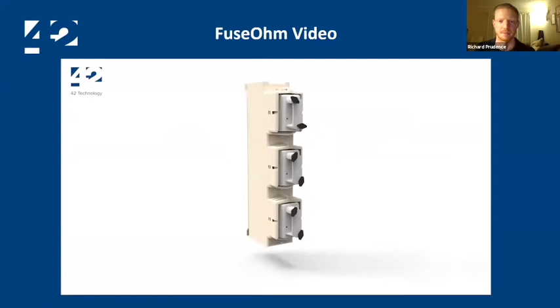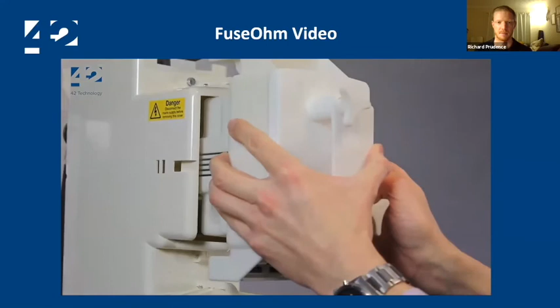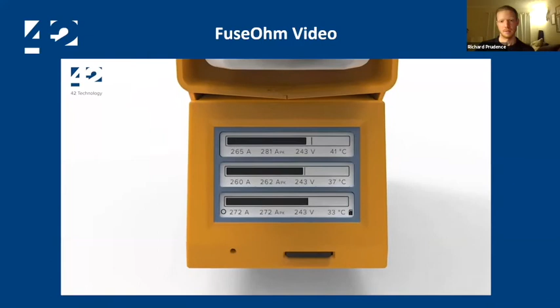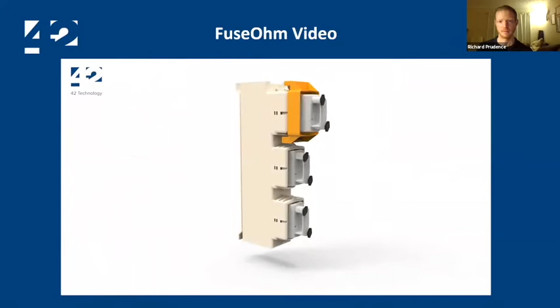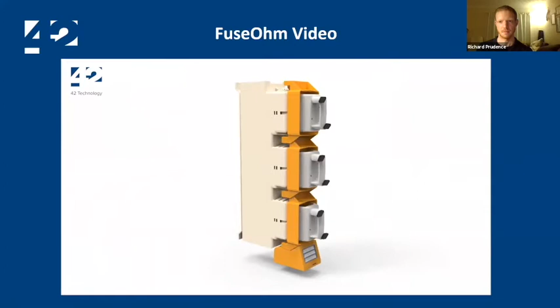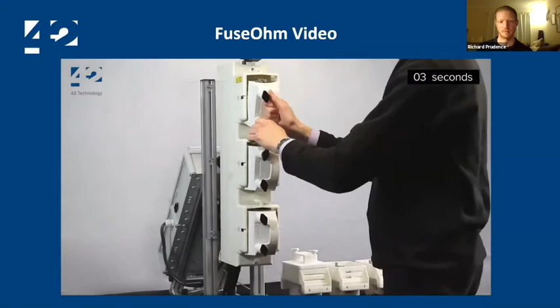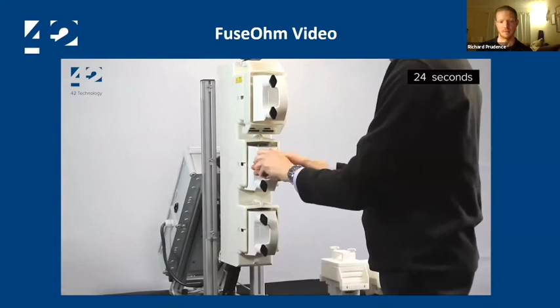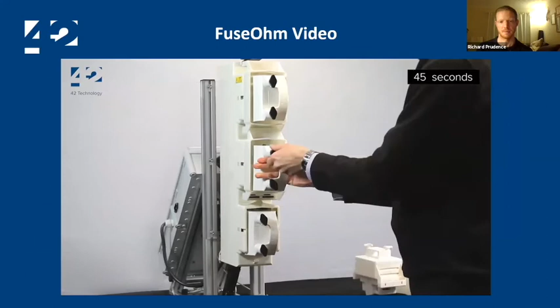Introducing FuseOhm, an innovative new three-phase monitoring system for electricity substations. Plug-and-play upgrading of existing fuseways in minutes, enabling smart asset management and fault analysis. The patent-pending system uses adapters that simply plug in between the existing fuseways and fuse holders. Data is transferred to the interface module for local display, logging, and external connectivity. Designed for retrofitting to typical UK substation components, the simple installation can be done in minutes, reducing labour costs and avoiding extended customer outages. It provides a true fit and forget system that avoids the need for external wiring or a separate power supply, unlike typical monitoring systems installed today.